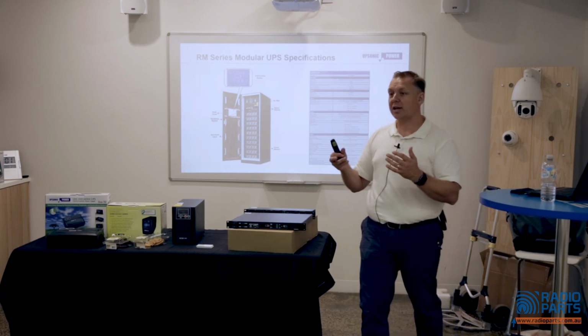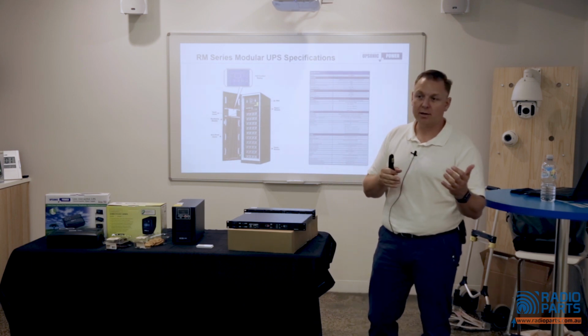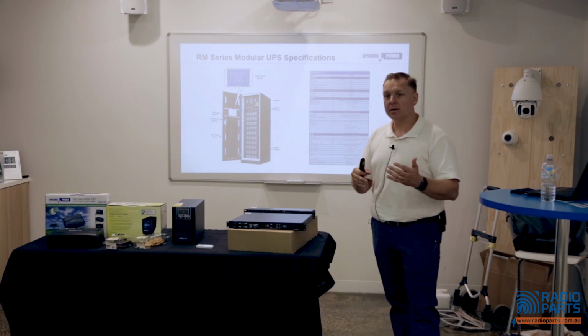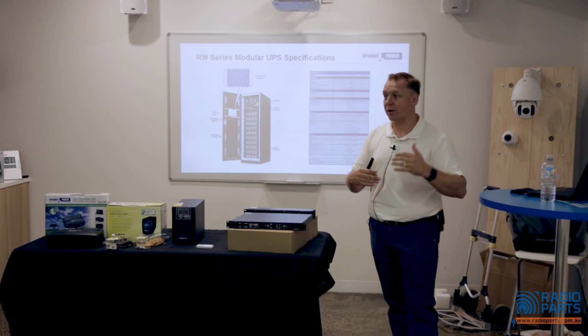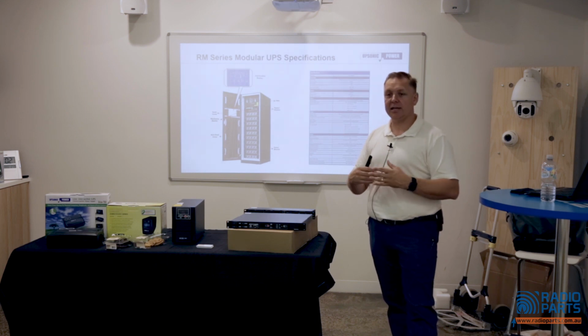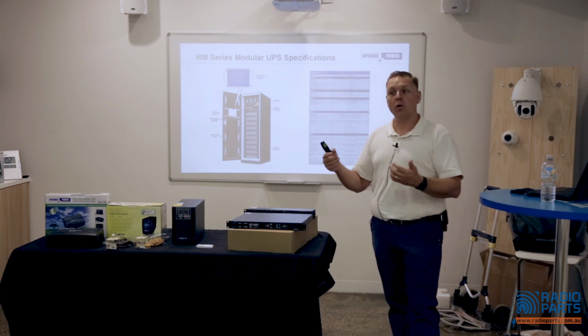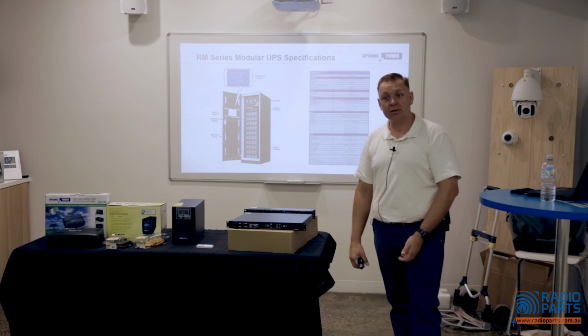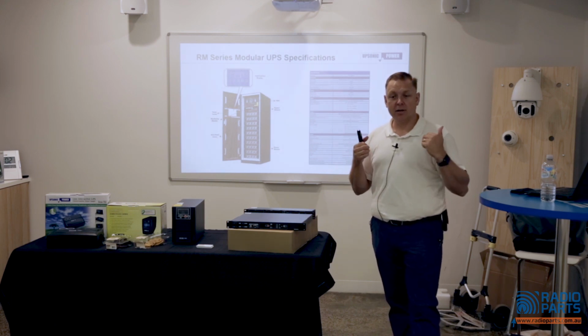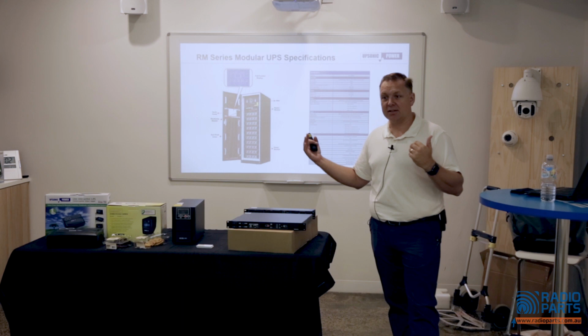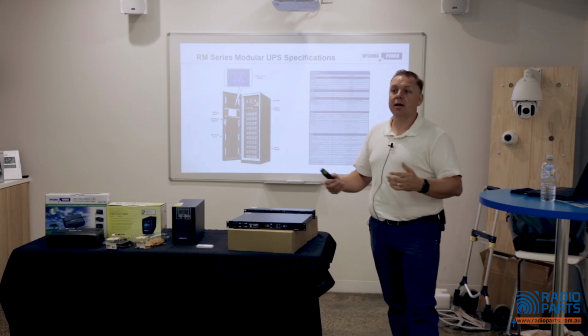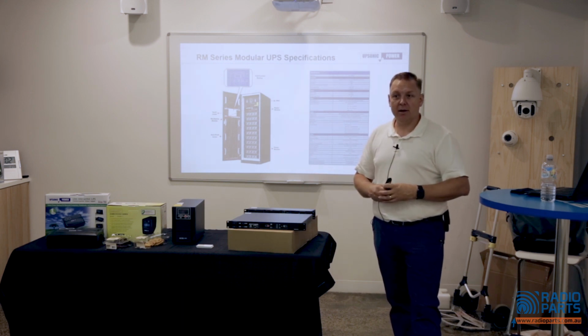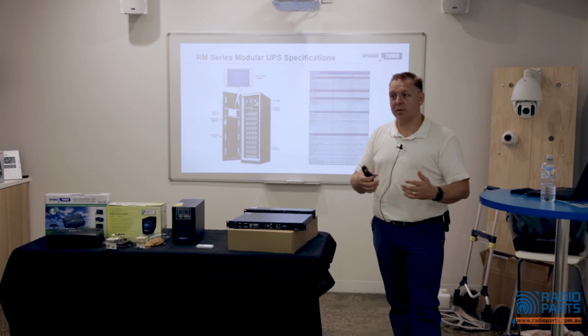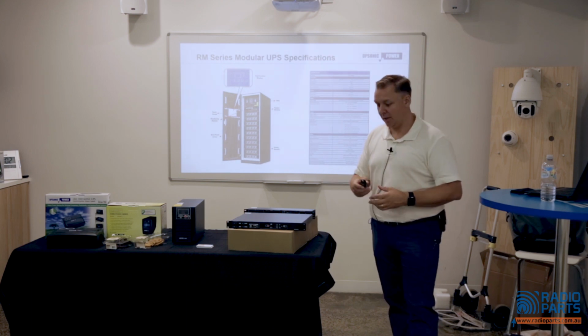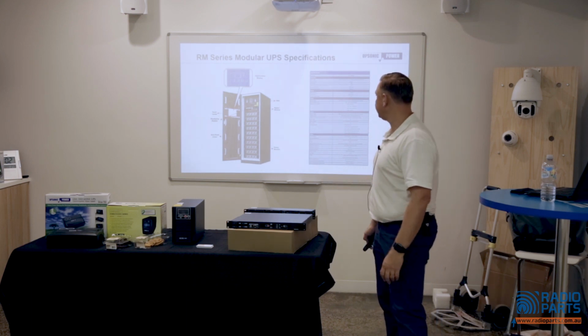So every week the UPS switches which module is supplying the load to make sure everything gets even wear and tear. And if one of those units fails, or just as importantly, you need to do maintenance on it, that module can be racked out. The load doesn't see anything, and that work can be done. A failed module can be replaced, plug straight back in, and the operation doesn't miss a beat.